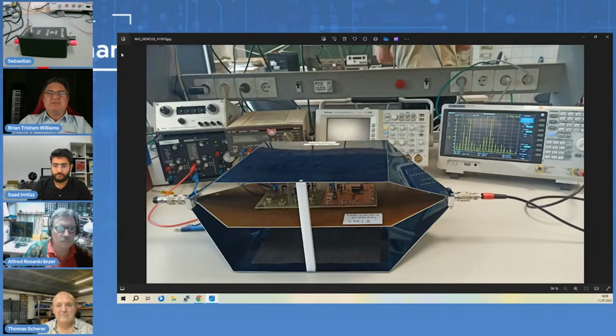The shape of the chamber? Yeah, it's basically, here it's a coax with 50 ohms, and this is just spreading it open. And here we technically have a free wave impedance of 377 ohms, but this is the wave impedance down here. What it really does is it takes the free room impedance of air and space and translates it back down to 50 ohms. It's symmetrical on both sides.